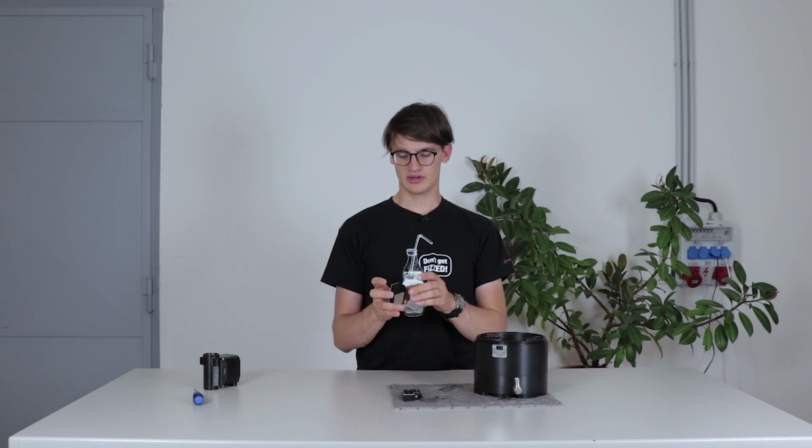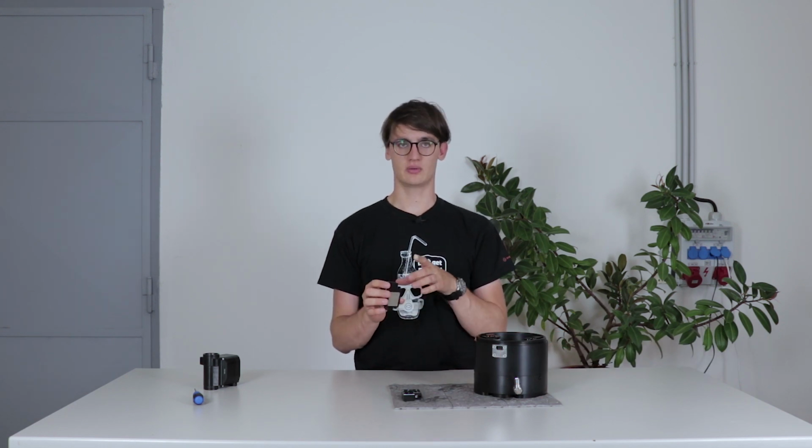Hello, in this video I'll show you what to do when one of your Helium sensors is not working properly. When your Helium sensor is either showing you an error message, or is not calibrating, or they're not in the same range of helium, it is very probably caused by high moisture inside of the sensor.